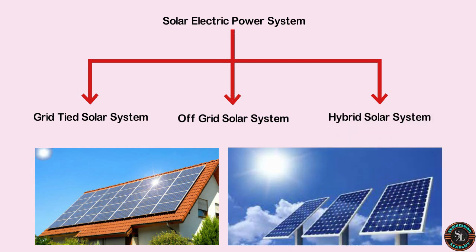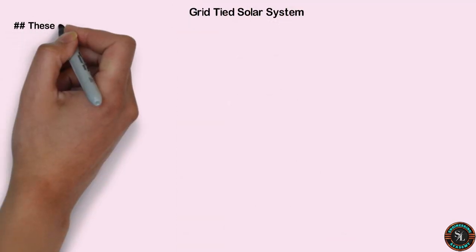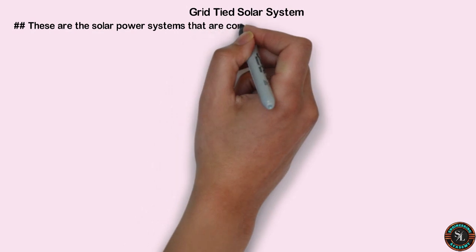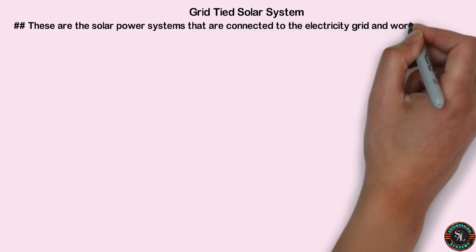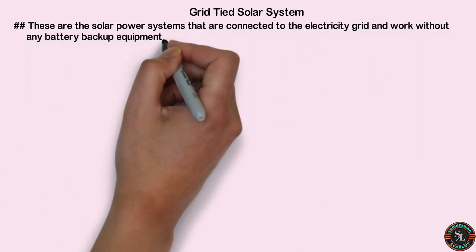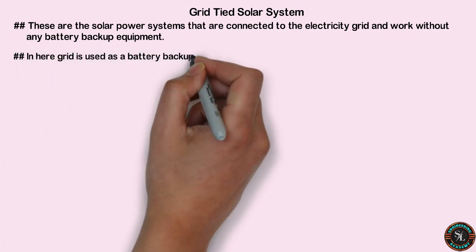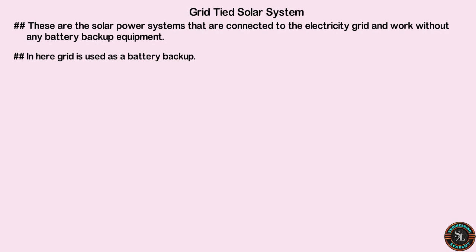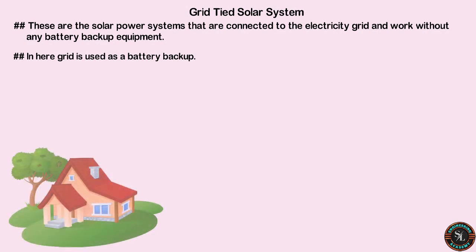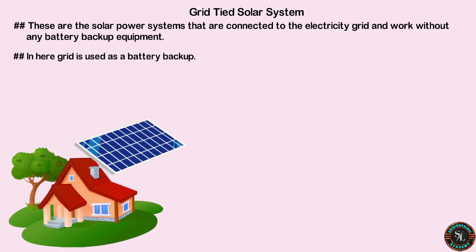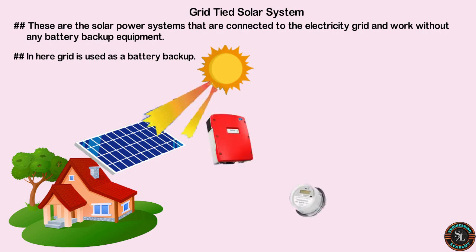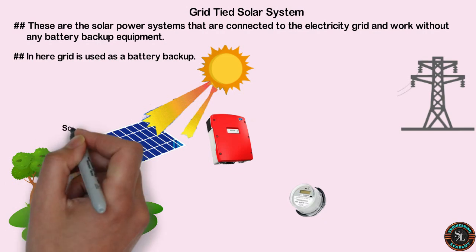First we will talk about the grid-tied solar system. These are solar power systems that are connected to the electricity grid and work without any battery backup equipment. This system mainly uses solar panels and an inverter. Solar panels are connected in a series circuit to increase the voltage and reduce the current. Here the grid is used as a battery backup. I will explain the grid-tied solar system using a diagram.